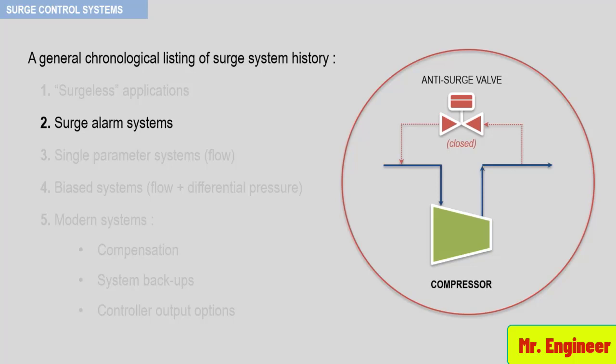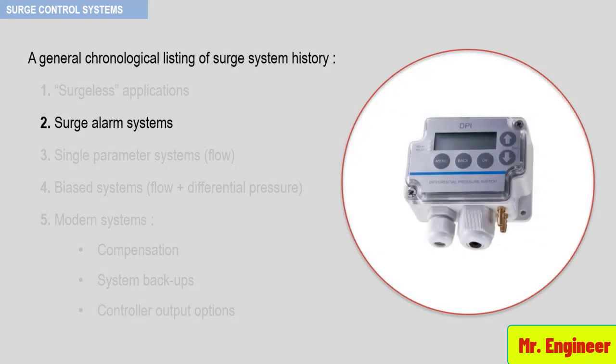A properly installed surge alarm system can eliminate these unnecessary shutdowns. Now, the reliability of these systems should be mentioned. Frequently, these detection systems are simply differential pressure switches as depicted here. Depending on the application, surge can be very violent or very light. However, in the case of low pressure applications or low molecular weight applications, the effect of surge will be minimal and the sensitivity of the surge sensor device must be investigated to make sure that the surge event is detected.